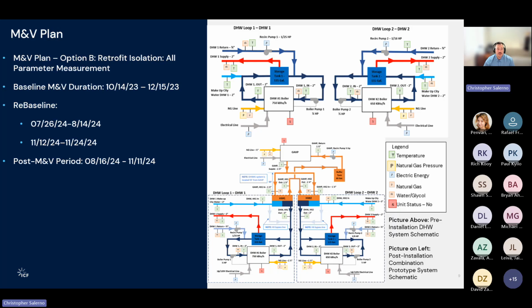And so now we'll go into the M&V plan. This is the diagram. I know it's a lot going on here. Up here, you can see there are two domestic hot water loops. As I mentioned before, this site has two different central systems that are outdoors, thankfully, which made it easy to retrofit with the equipment that we use for this project. One system is at 750 kBTU per hour with a 115 gallon tank. It has a standard recirculation pump, and then the hot water supply. These two systems were independent of each other during the baseline. They serve roughly 35 units each. And this is the other system. It's essentially the same thing, but with a slightly smaller boiler capacity at 650 kBTU, still with a 150 gallon tank.